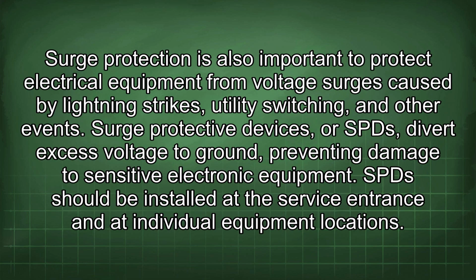Surge protection is also important to protect electrical equipment from voltage surges caused by lightning strikes, utility switching, and other events. Surge protective devices, or SPDs, divert excess voltage to ground, preventing damage to sensitive electronic equipment. SPDs should be installed at the service entrance and at individual equipment locations.